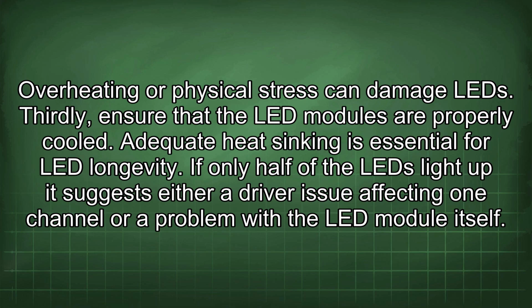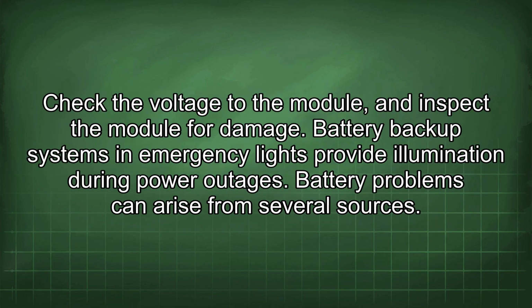If only half of the LED light up, it suggests either a driver issue affecting one channel or a problem with the LED module itself. Check the voltage to the module and inspect the module for damage.